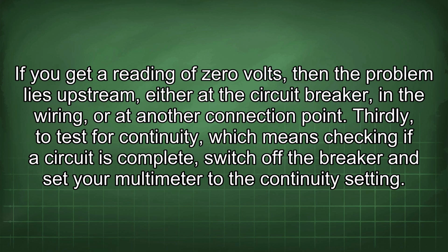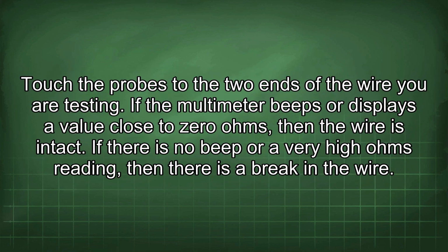Thirdly, to test for continuity, which means checking if a circuit is complete, switch off the breaker and set your multimeter to the continuity setting. Touch the probes to the two ends of the wire you are testing. If the multimeter beeps or displays a value close to 0 ohms, then the wire is intact. If there is no beep or a very high ohms reading, then there is a break in the wire.